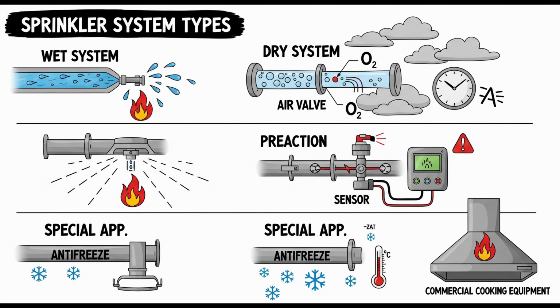Why is that critical? Because in a pre-action system, the detection is the first step. It needs to sense the fire and cause the main valve to open, filling the pipes with water before the fire gets hot enough to actually open the sprinkler heads. So the pipes are charged and ready when the sprinkler opens?